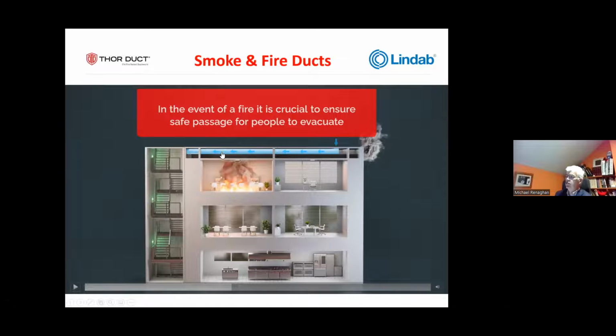That duct will cross, or may cross, a fire compartment, a compartment where the fire is raging. So it needs to be insulated to prevent this air from becoming superheated and therefore becoming a problem in the escape routes. So this is a pressurization duct, and again, insulated to prevent the air inside the duct heating up.